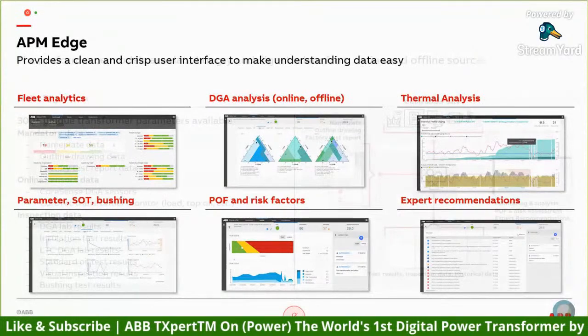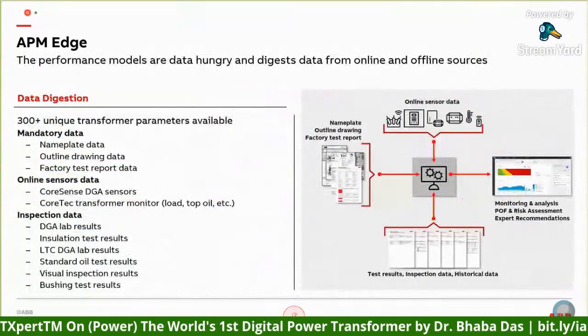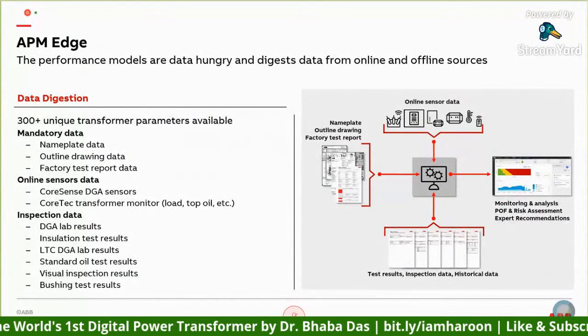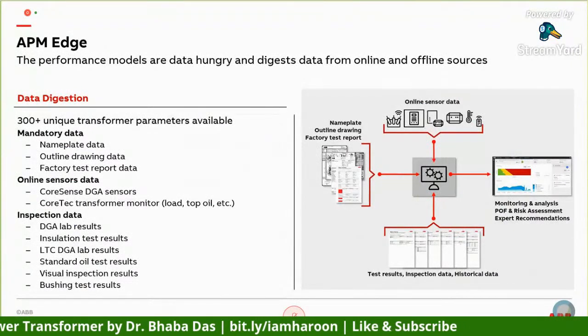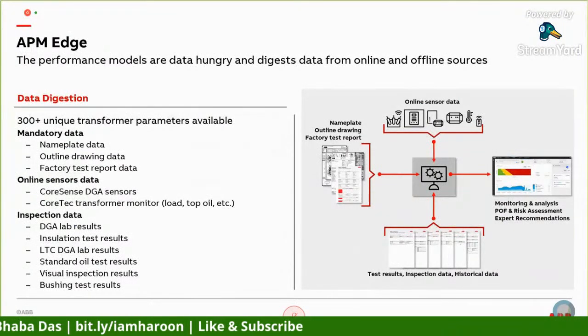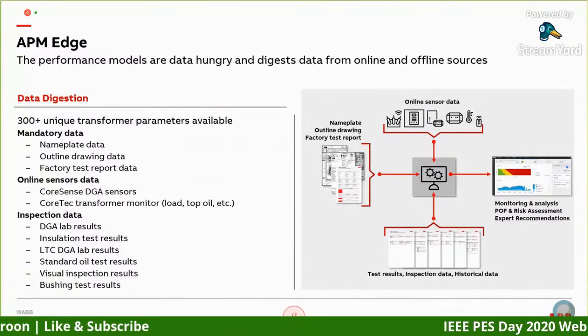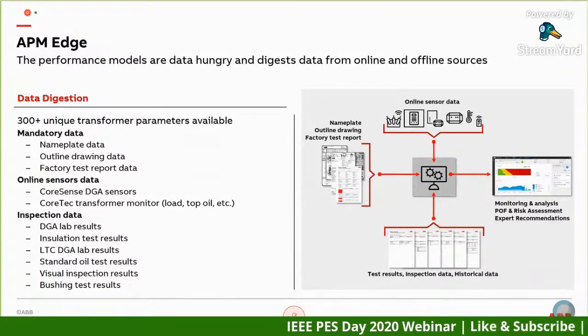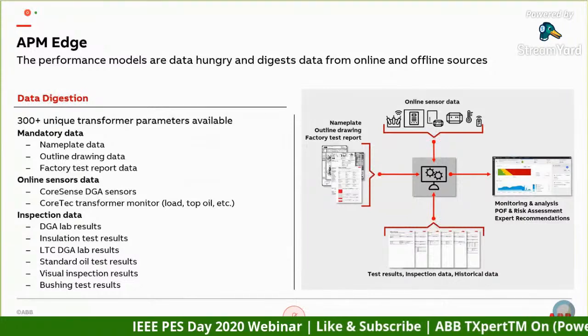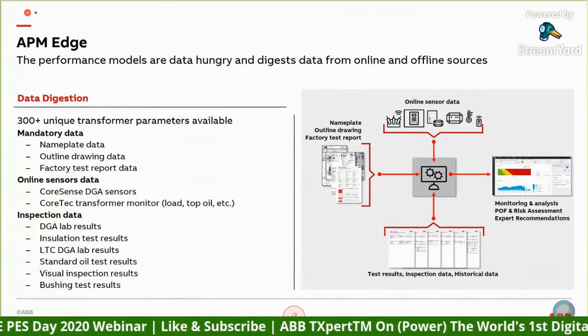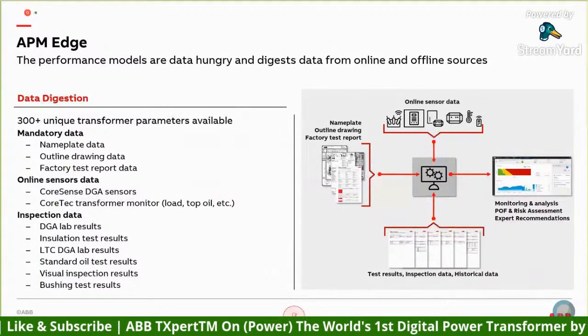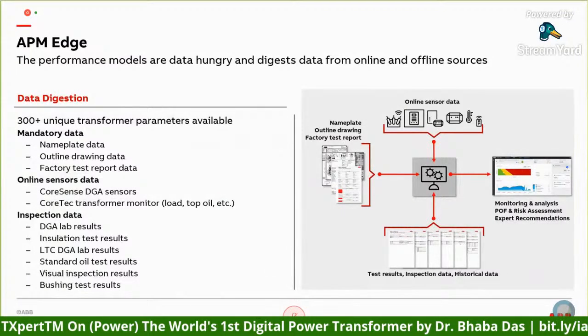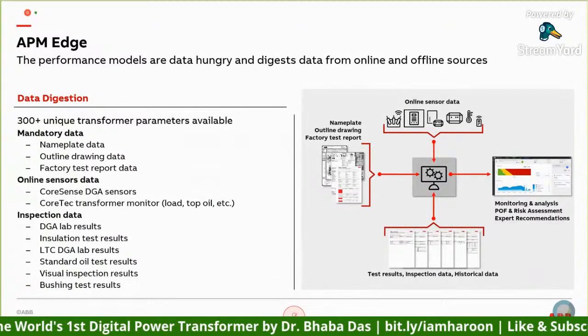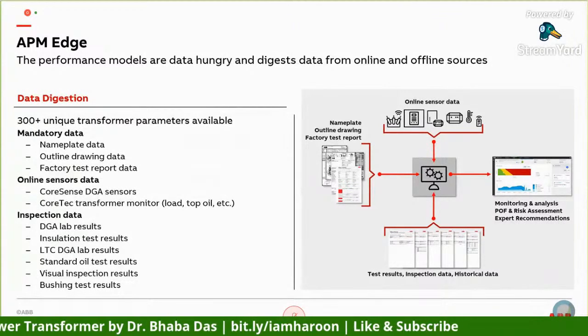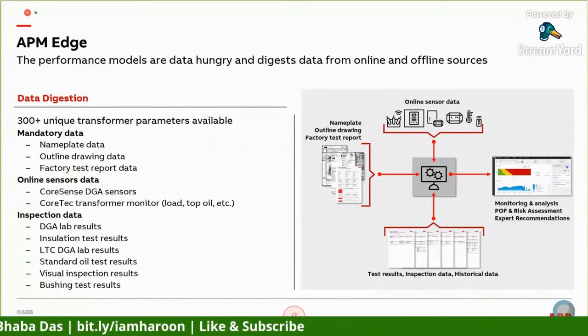So what is the software doing? It needs data. There are some mandatory data: nameplate, factory test report, drawing data, all of that. If you have online DGA sensors, we put in the DGA sensors, and then inspection data like the DGA test results, visual inspection results. No other software will ask you if you have corrosion in your tank, what is the risk of failure to my transformer?